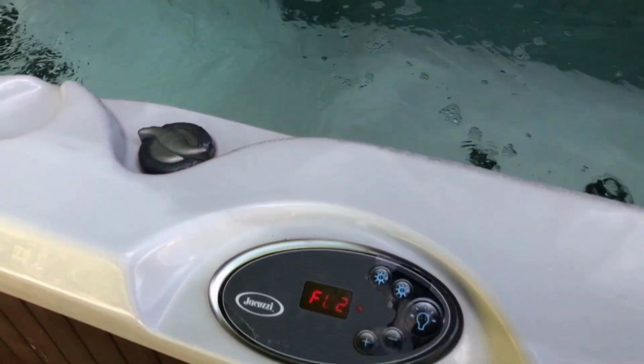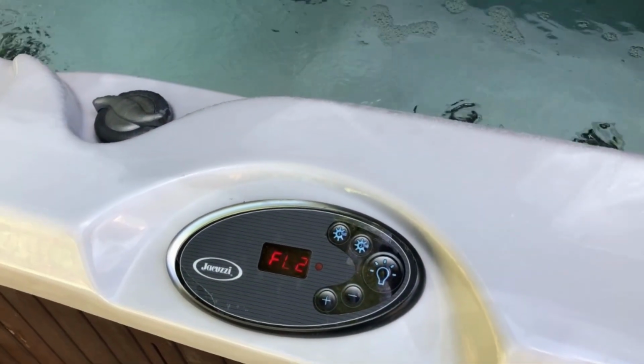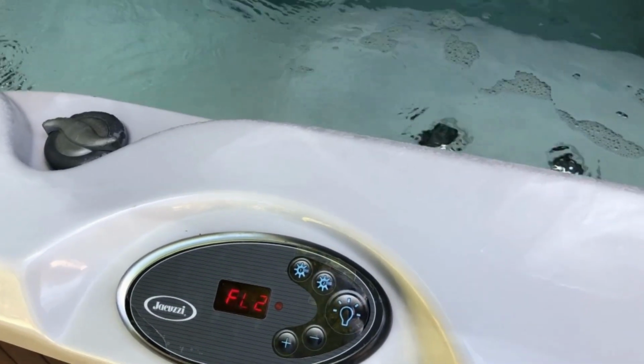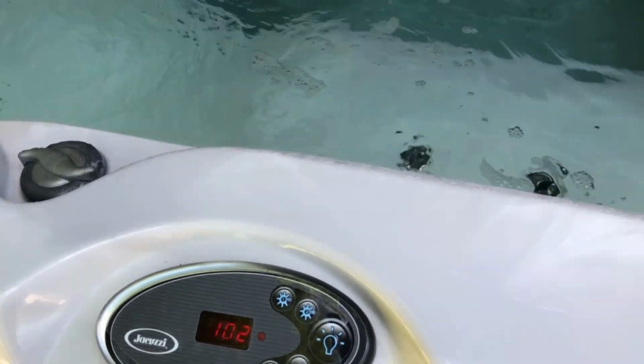Then one day the issue changed intermittently—the pumps were not running at all and wouldn't turn on. But taking the covers off and putting my voltmeter on the outputs from the control board, there was no electricity there, so it wasn't a problem with the pump.